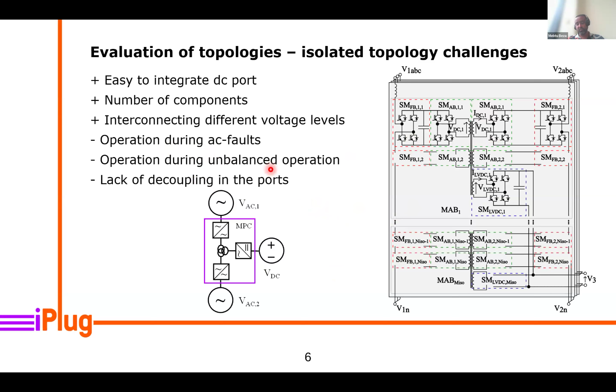Continuing with this evolution, the next step is to use a back-to-back setup like the first one, but instead of half bridge cells, we use full bridge cells. This increases the number of components, since full bridge cells use twice the components of a half bridge cell. But the advantage is that we can decouple the AC voltage level from the DC voltage, meaning we can reach a lower DC voltage, making it easier to realize using an isolated stage and easier to deal with DC faults than when using half bridge cells.